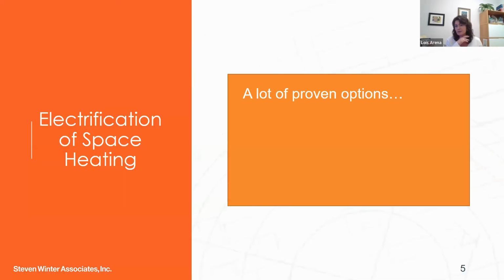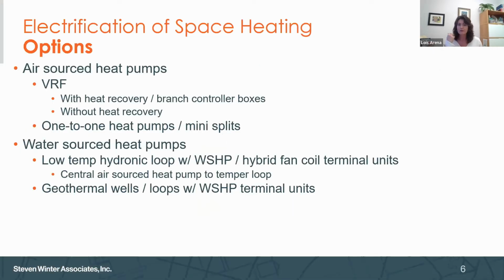So space heating, let's jump into this since most of you are familiar with it. Our basic options that we see regularly in our projects are VRF, variable refrigerant flow air source heat pumps. Most of the time we recommend heat recovery so you can do simultaneous heating or cooling. Some projects get that value-engineered out depending on budgets, so you can also run VRF without heat recovery, where you're either in heat pump mode or cooling mode. You can also do one-to-one heat pumps and mini splits depending on the height of the building.